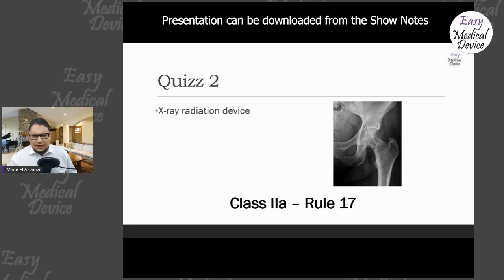Is there any other rule that is applicable? Rule 10. Let me check rule 10. Active devices intended for diagnosis and monitoring are class 2A. Okay. Rule 10, if they are intended for supply of energy which is absorbed by the human body, except for devices intended for illuminating the patient. Okay. If they are intended to image in vivo distribution of radiopharmaceuticals, so it's not X-ray, this one. If they are intended to allow direct diagnosis or monitoring of vital functions, etc. So you see there are many rules that are applicable to that.